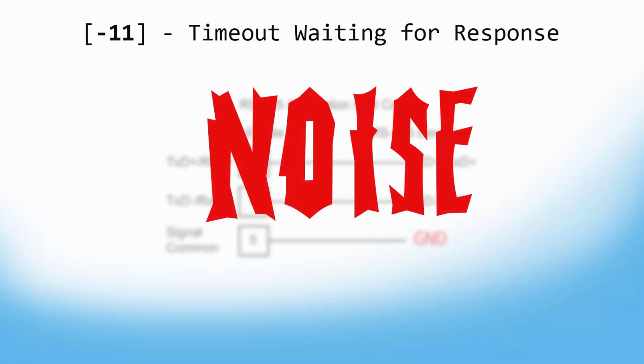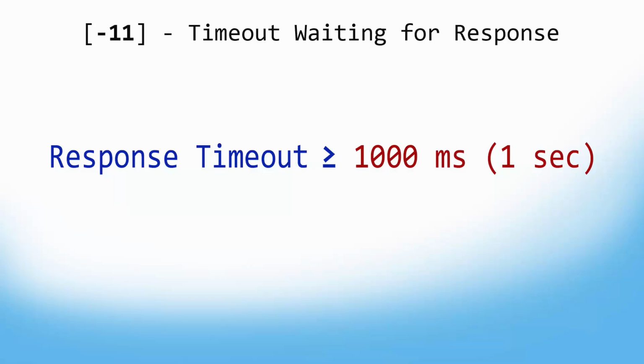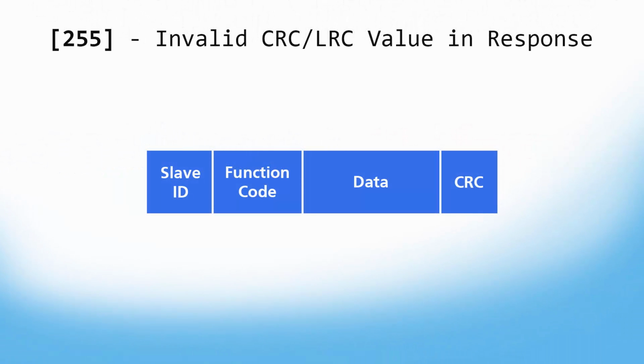And finally, you should ensure that the response timeout on the module is set no lower than 1000 milliseconds, or 1 second. Anything lower and communications may not be able to keep up consistently. Moving on, we come to error code 255.